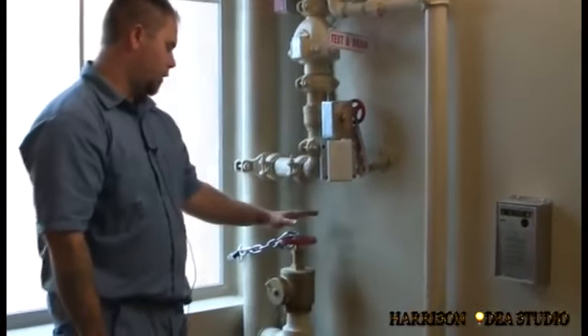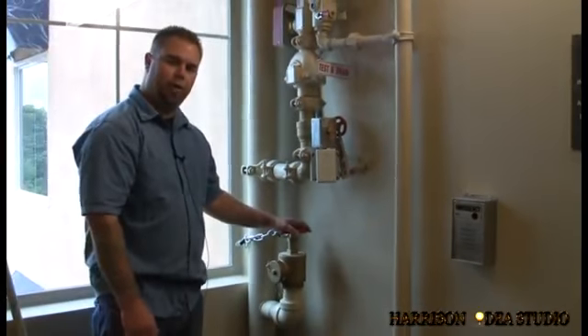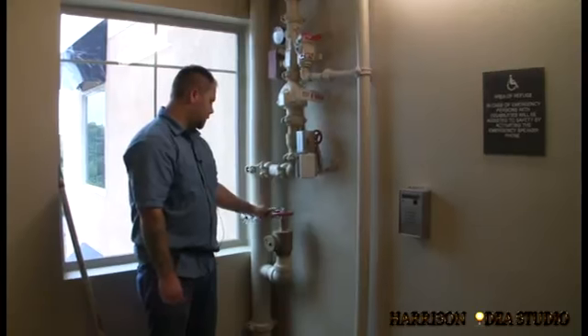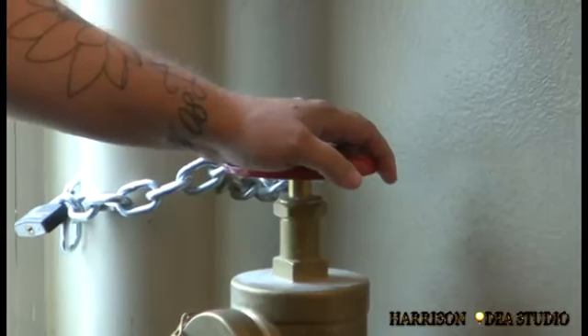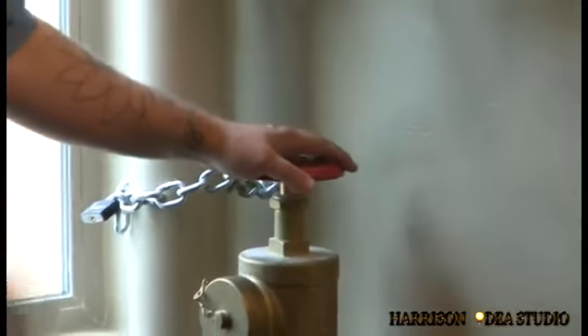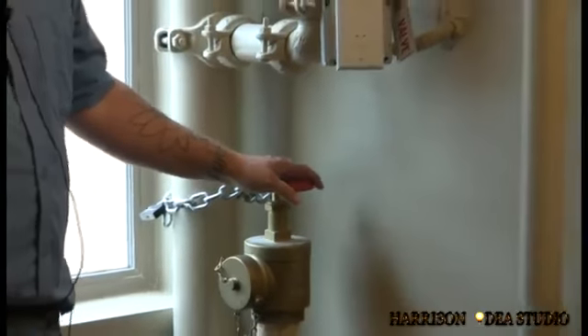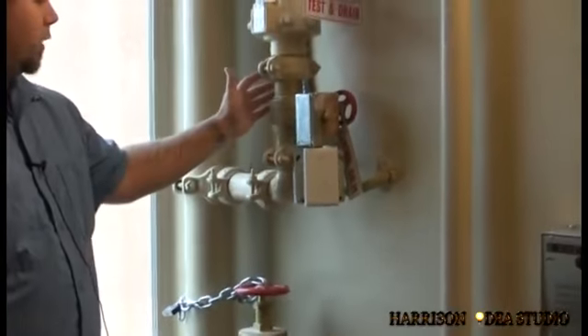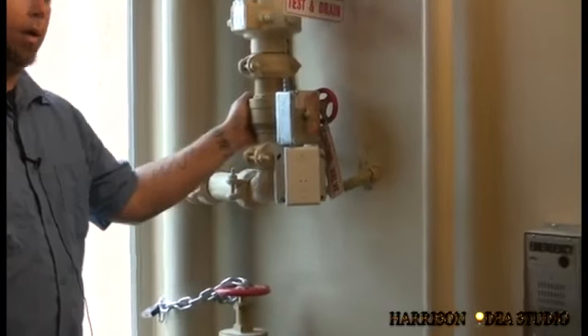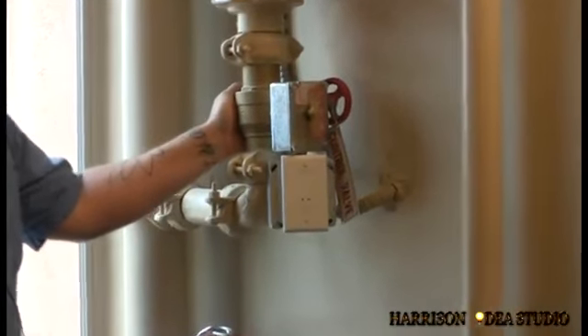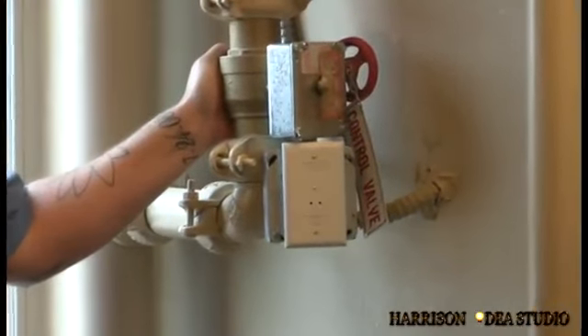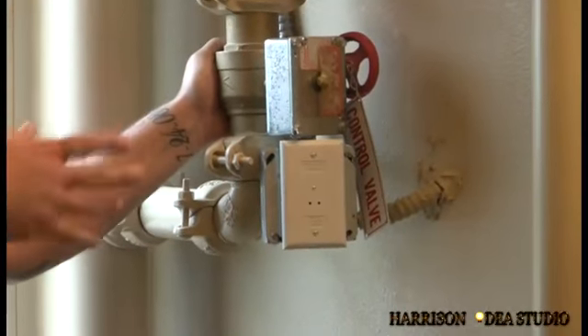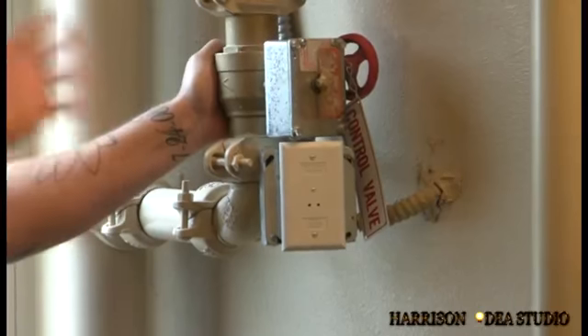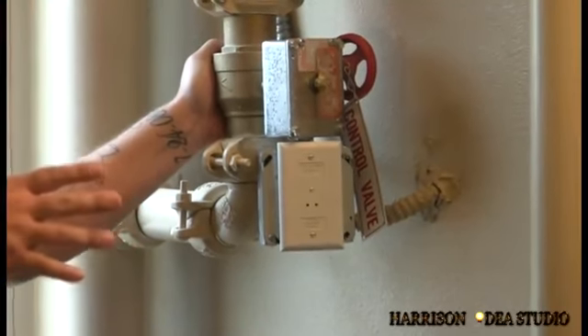Down here you've got your fire department connection hose valve. It's locked out so that none of the tenants can open it up and discharge a bunch of water, but the fire department can come in here and break this off and use it to hook up their fire hoses and fight a fire. Above that is your isolation valve for this floor. Every floor has one. If there's any kind of maintenance that needs to be done to the system, we will shut off the supply to this floor by itself so that we can do our service, leaving the rest of the building in service.